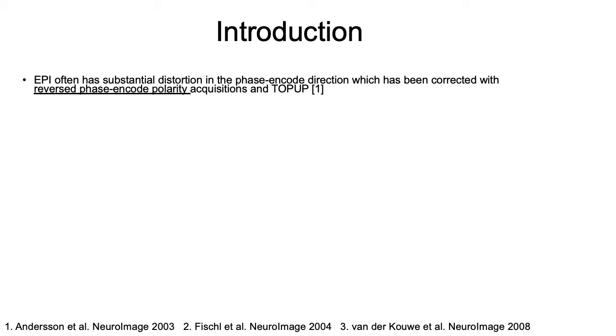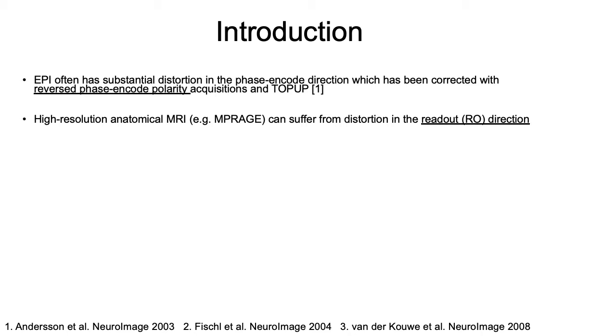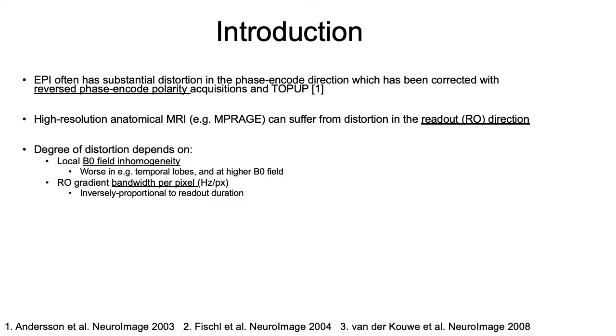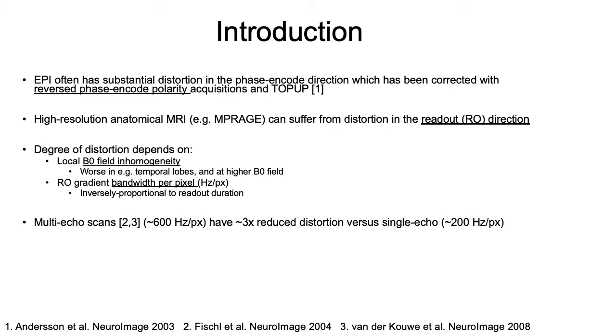We've seen that EPI distortion can be corrected with reversed phase-encoding polarity acquisitions and TOPUP. Anatomical MRI can also have distortion, but now in the readout direction. The amount of distortion depends on the local B0 field inhomogeneity and the readout gradient bandwidth per pixel.